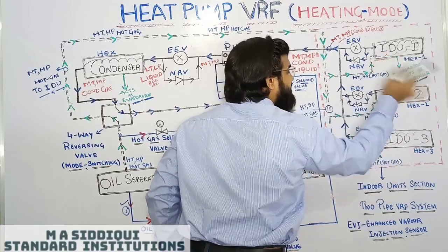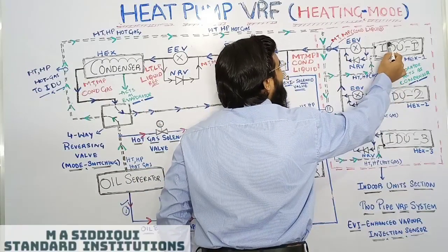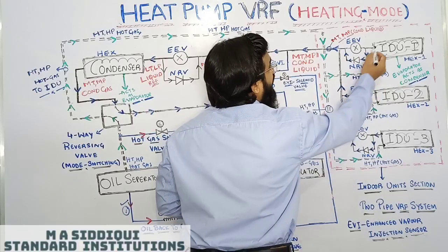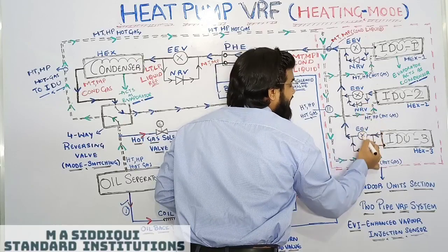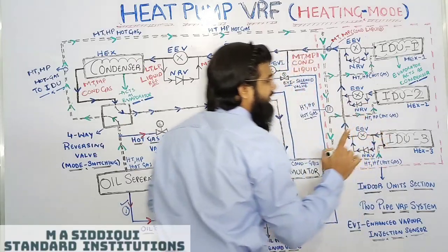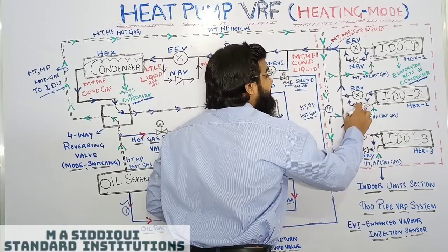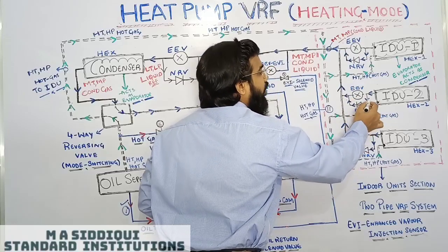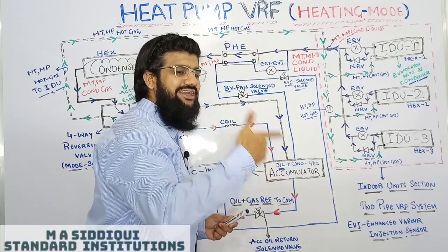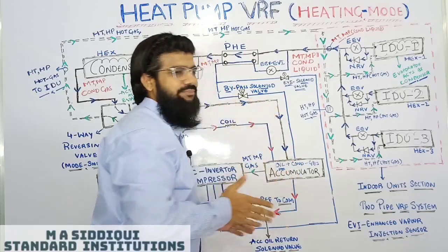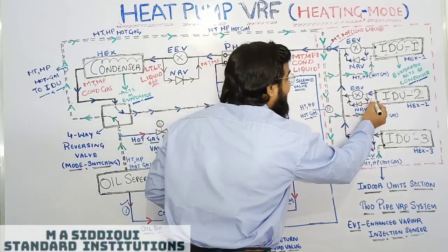Now, due to heat exchange between the coil and the room air, what happened? That hot gas converted into condensed gas. This condensed gas, when it comes out of the IDU, will not go to the EEV, the electronic expansion valve. Why? Because the placement of the NRV is the same as the directional flow of the refrigerant coming out from the IDU. It means the direction of the refrigerant and the direction of the NRV are the same.